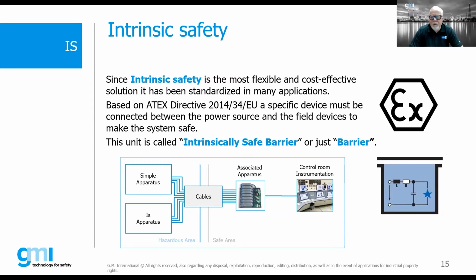And when we're using intrinsically safe, we have to make sure that we follow all the parameters: what is the signal type, what is the associated apparatus that we need to use, what types of cables are we using, how are we going to be installing it, and what is our end device? Is it a simple or a certified intrinsically safe apparatus? We have to take all that into consideration to select the appropriate associated apparatus to match it. So we do call this a loop concept, and we have some other terms that we'll get into in just a second.